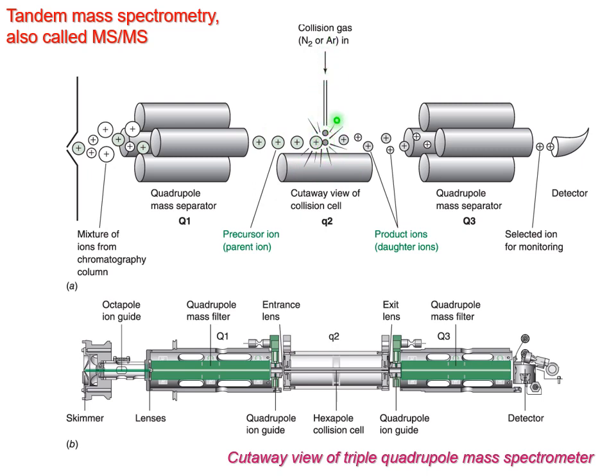Collision occurs with gas or with ions. As a result, our ions here fall apart into fragments, and then produced daughter ions are again separated by the second quadrupole mass separator. Only one type of fragments came here. Sometimes, because there are three quadrupoles, it's called MS multiple quadrupole—triple quadrupole—another name for the same thing.